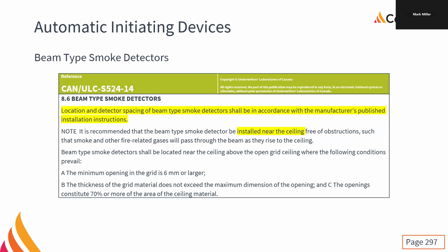We have to install them in accordance with manufacturer's instructions, of course, and that's the big one. And we install them near the ceiling and free of obstructions, but such that smoke and other fire-related gases will pass through the beam as they rise to the ceiling. So we're not putting them right up at the ceiling. We're putting them a little bit down. And the manufacturer says exactly where they have to go, how high up they have to go, and all that, usually expressed as a percentage of the ceiling height.